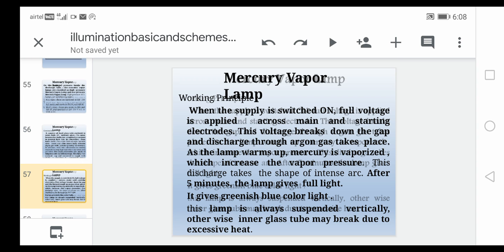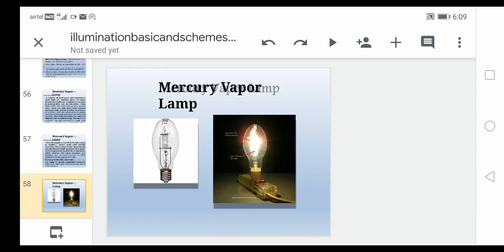The working principle of the mercury vapor lamp is that whenever the switch is on and full voltage is applied across the main and starting electrodes, this voltage breaks down the gap and discharge through argon gas takes place. As the lamp warms up, mercury is vaporized, which increases the vapor pressure. These discharges take the shape of an intense arc. After 5 minutes, the lamp gives full light. It gives a greenish blue color light. This lamp is always suspended vertically, otherwise the inner glass tube may break due to excessive heat. This is a mercury vapor lamp.